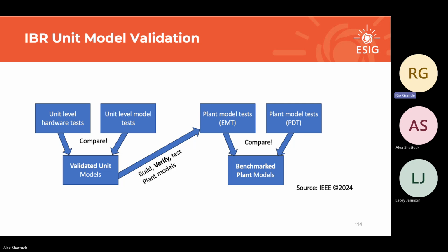The power plant controller is validated individually and the inverter individually as well. What's your take on that? That's an argument I lost. That was the consensus that we got to. So validating them separately is okay, right? Because at the end of the day, the communication between the inverter and the plant controller is doing all the math and it's sending a current command to the inverter, right? So we'll catch a lot of everything, right? So it's fine. It's a really good step in the right direction.